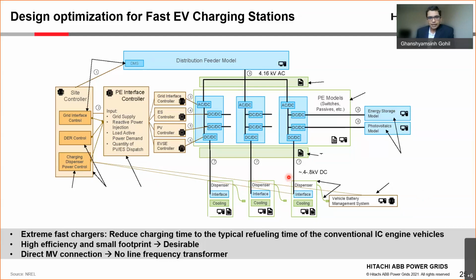A major obstacle to achieving a small footprint is the line frequency transformer used in state-of-the-art chargers. In this work, we avoid using the line frequency transformer and instead use medium voltage power converters for direct medium voltage interconnection.